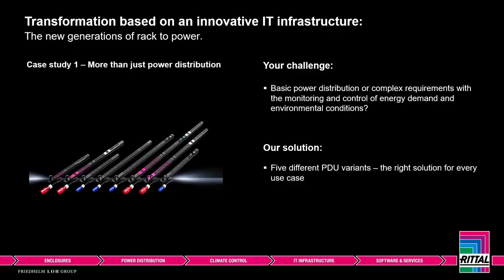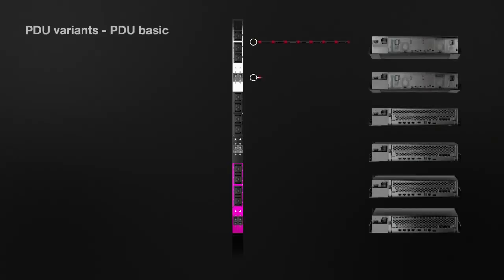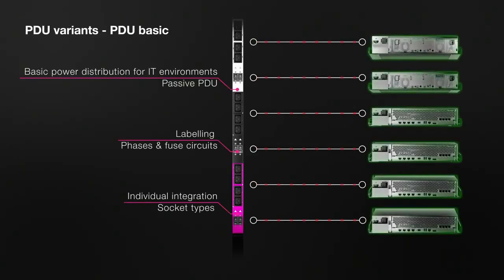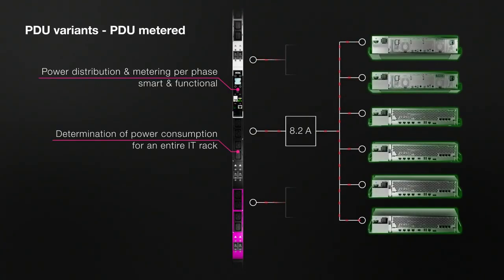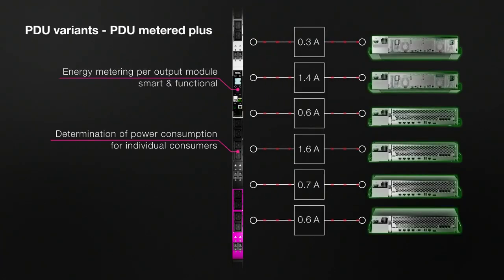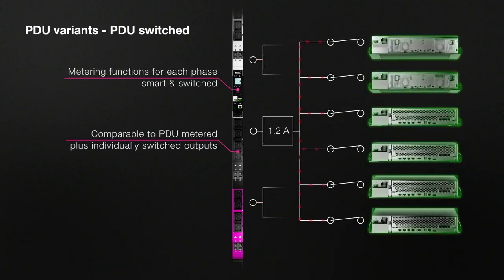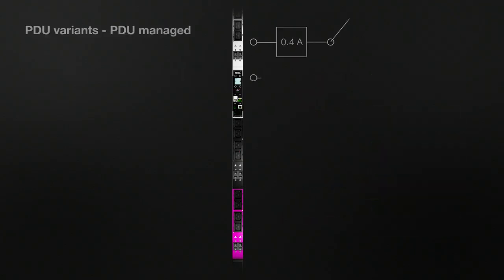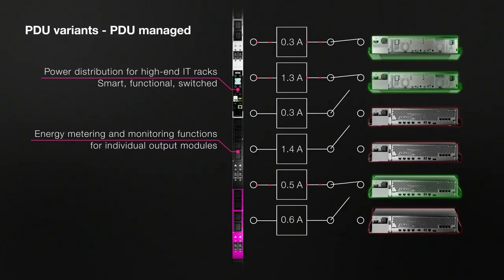Our product range consists of 5 PDU variants. Basic power distribution is possible with the PDU Basic. The range of intelligent PDUs consists of the PDU Metered, with measurement at the phase level, or the PDU Metered Plus, with measuring at the outlet level. The PDU Switched offers measurement at the phase level and the option of switching per outlet. Finally, the PDU Managed combines all functions, with measuring and switching at outlet level.